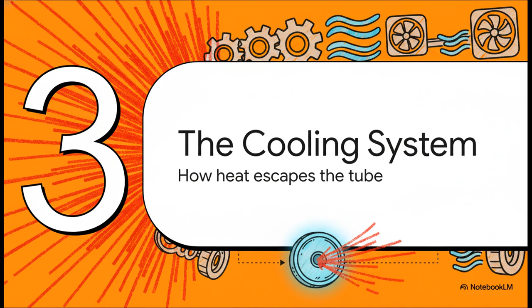It's brilliant. And it does this at mind-blowing speeds. To keep up with something like a modern CT scanner, these anodes can spin up to 10,000 revolutions per minute. That's spinning faster than the engine in many high-performance cars. It's just an incredible piece of engineering, and it's all happening inside a perfectly sealed vacuum. But here's the thing. The rotating anode, as amazing as it is, doesn't work alone. It's definitely the star of the show, but it has a whole supporting cast of other cooling systems, all working together to get that heat out of the tube and away from everybody.